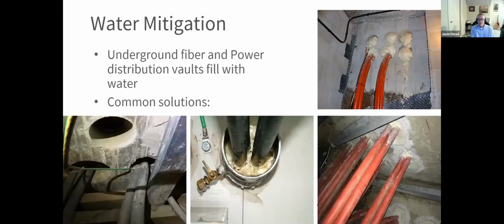So what I'm going to share with you now is some application, a little bit about the real world of what we see here. But when there is no standard, again, I referenced that before, there is no standard on how to prevent water infiltration. And this is what we see as a company. You see pictures here, conduits and duct banks with nothing, no seal at all.